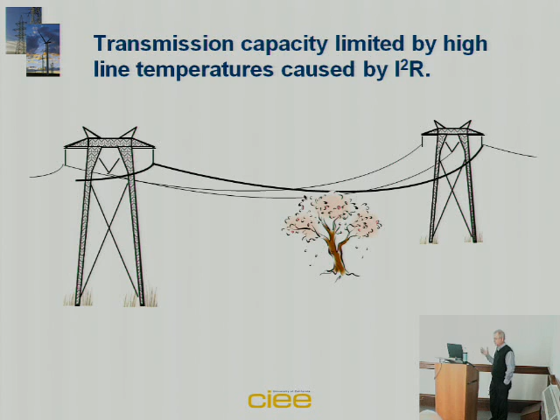And then there's one that I really didn't put on here, but there is the N-1 reliability constraint, which is at the moment considered an acceptable way of running a transmission system. Well, the first I'll talk about is the thermal limit. The transmission capacity is limited by high line temperatures caused by fundamentally I squared R, the toaster effect. And what happens is if you run too much power, the line heats up, it sags into a tree, it causes a short to ground, and it can cause a fire. Those are not good things.